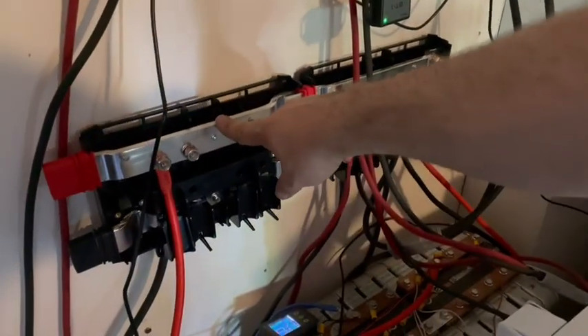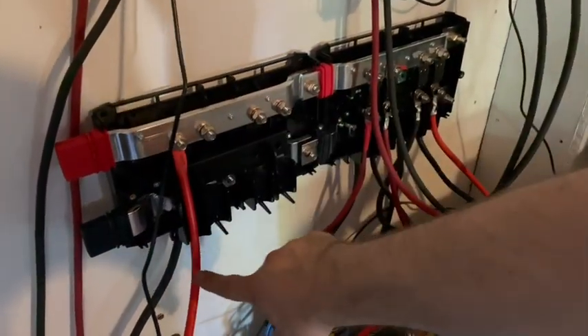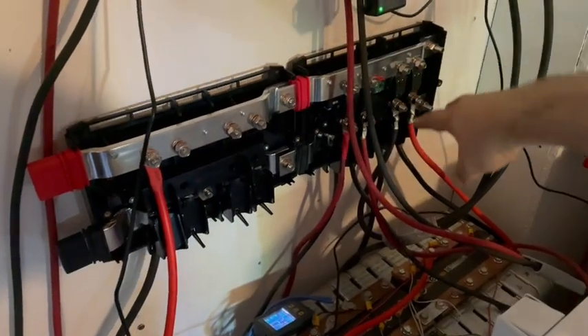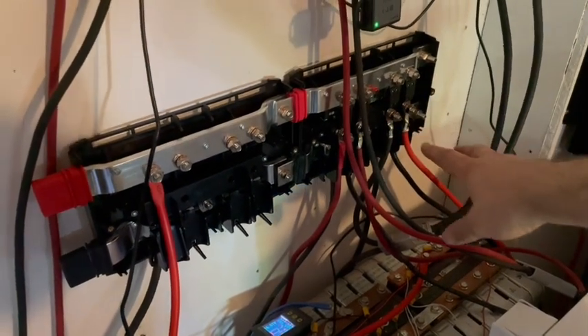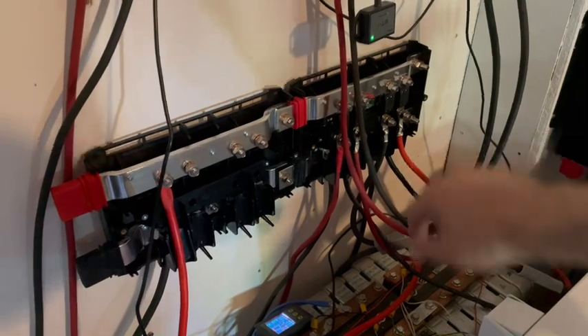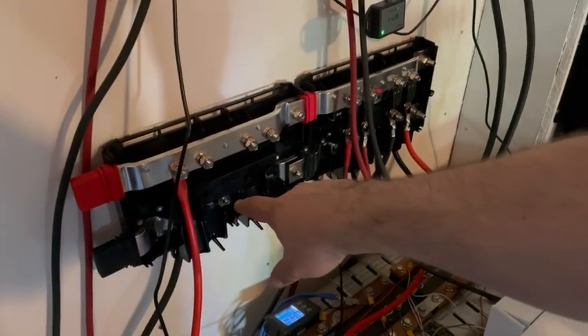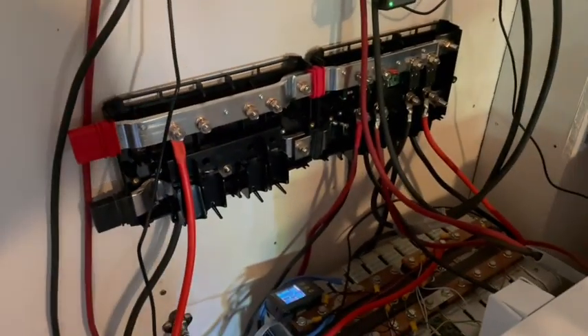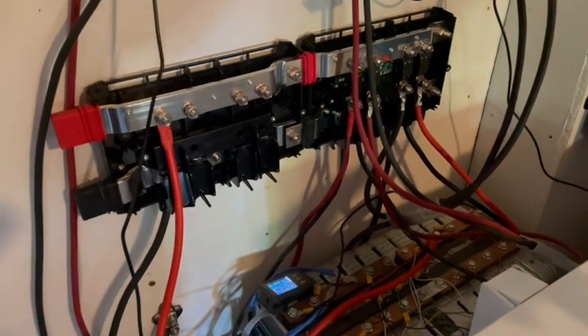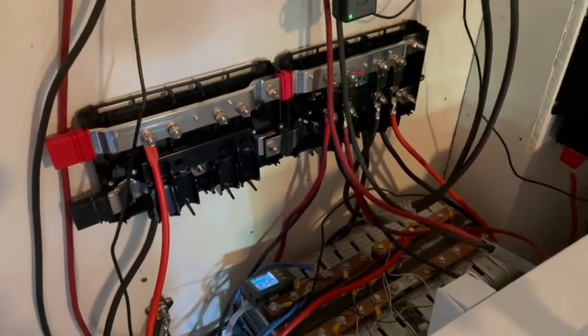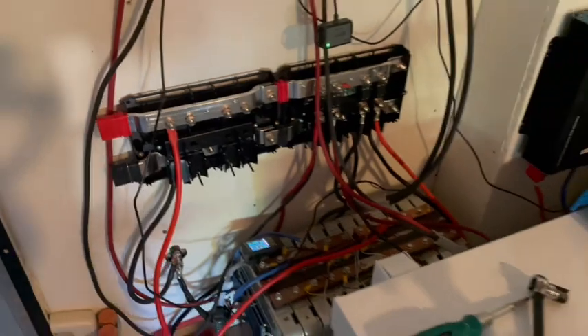The distributor, or the power in, has only the battery, and the distributor has all the loads and chargers. There's only 1 load and 3 chargers right now. This one, later I will add another lithium ion battery to it, which currently is down here - that battery doesn't belong there, it should be over here, tied in parallel to this one. Each battery will have its own BMS, so it's safe to parallelize them because they're BMS'd inside the parallelism.